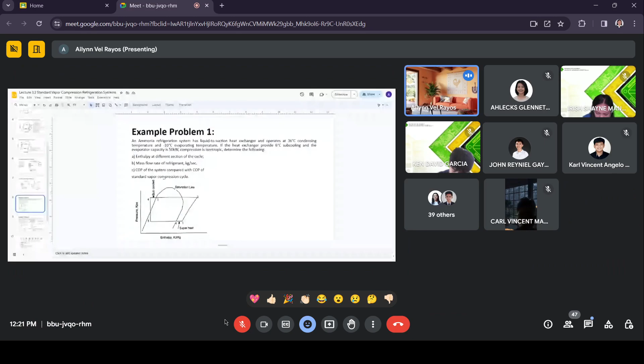So what are the givens in our problem? This system has subcooling and superheat, but based on the problem, we only have subcooling. It subcooled by 6 degrees Celsius. So when we say subcooling, it means the temperature dropped by 6 degrees compared with its condensing temperature. So the givens are: our condensing temperature is 36 degrees Celsius.